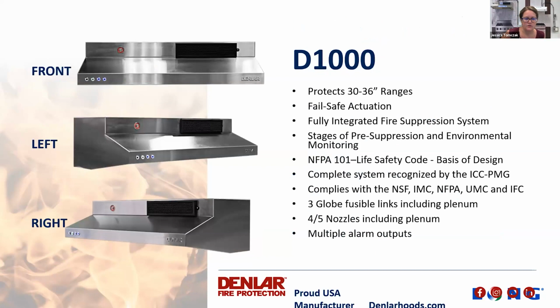The next core model we have is our D1000. Again, there are multiple configurations and options within this unit, designed to protect either a 30 or a 36-inch range. It maintains a fail-safe actuation, so you've heard me say that a couple times. What that means is that what's putting out the fire is a fully mechanical process. There's no electricity involved in putting out a fire within our hoods. We are maintaining that integrated fire suppression system, which means there's no calibration of where the nozzles are or installation of the suppression system itself in the field.